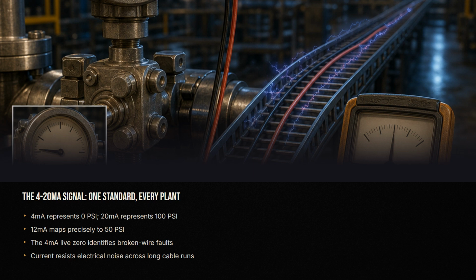The lower bound is deliberately not 0. If 0 were the minimum, a broken wire would be indistinguishable from a valid 0 reading. The 4 milliamp baseline, called the live 0, prevents that confusion. Current signals resist electrical noise over long cable runs. That matters in environments with variable frequency drives and high-voltage equipment running nearby.